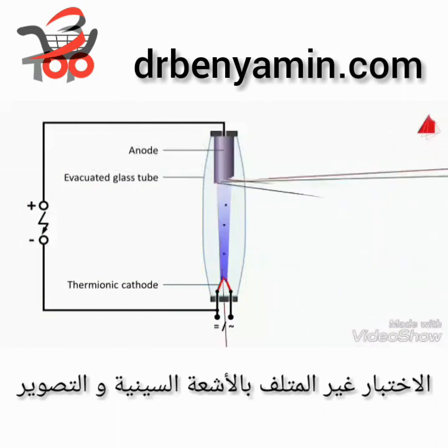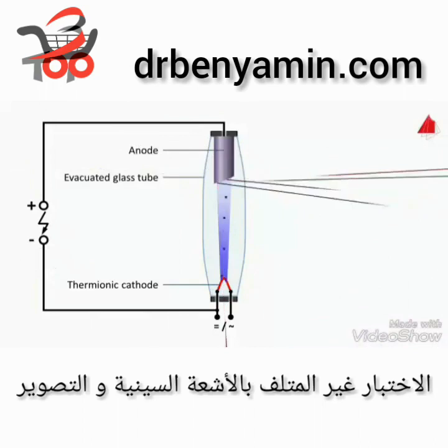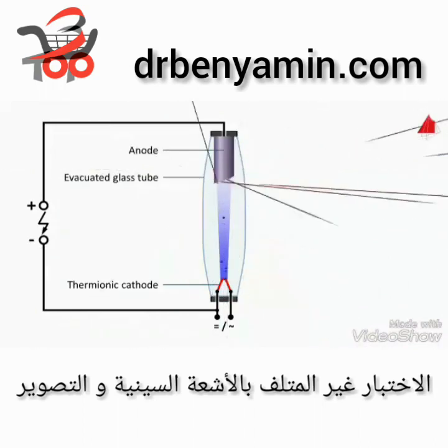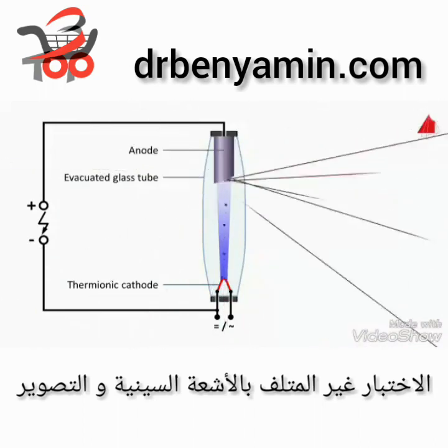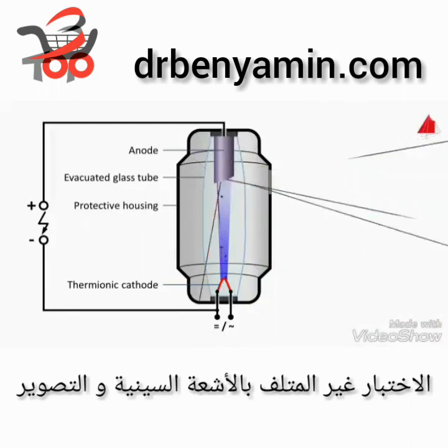Because the anode surface is slightly inclined, the emission of the X radiation towards the right is more intense, but a certain proportion also radiates in other directions. A protective housing shields X-rays going in unwanted directions. The desired X radiation can only reach the outside through a small transparent window.